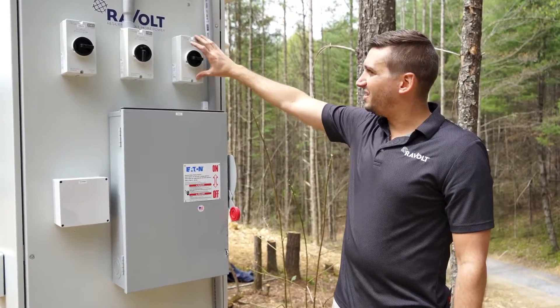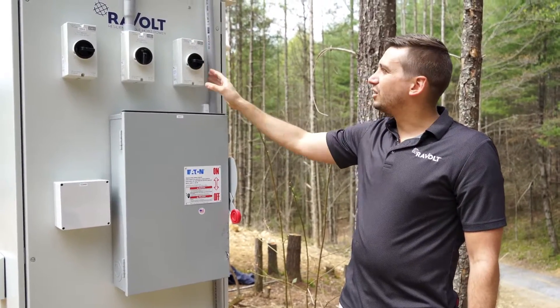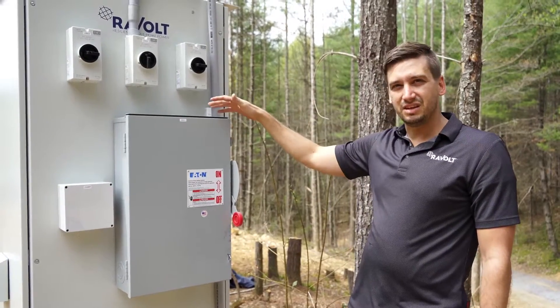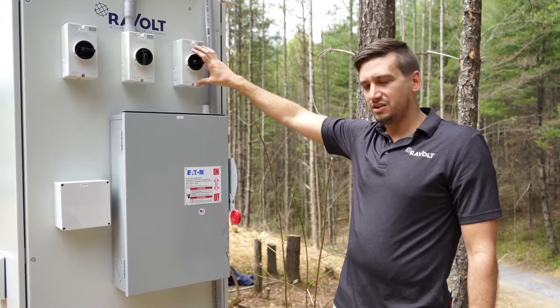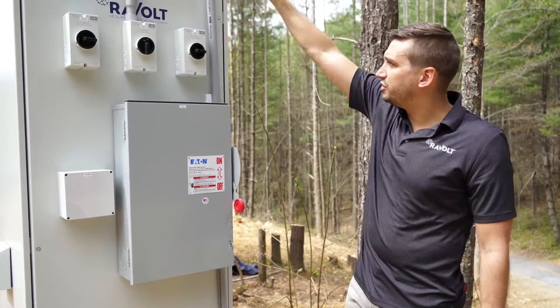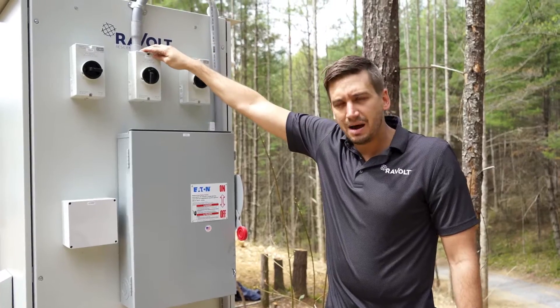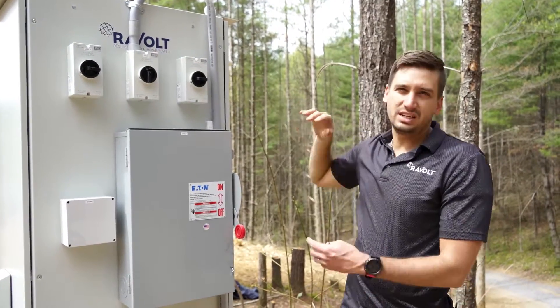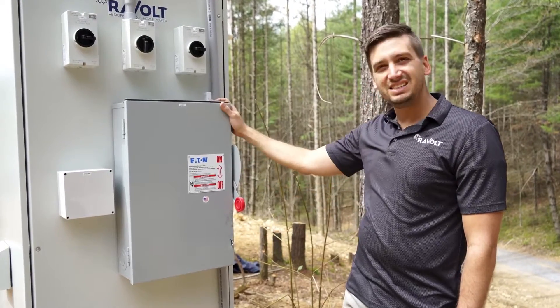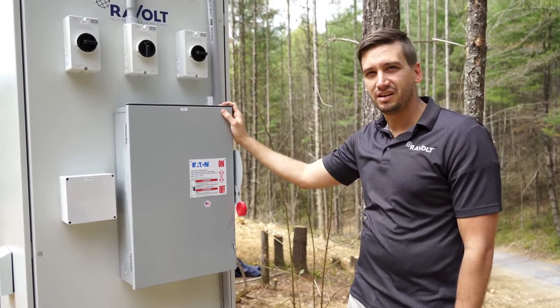Also on this side of the equipment are three PV disconnects that are already pre-wired from the MPPTs of the inverter out to the outside of the equipment. All the customer needs to do is bring a single piece of conduit in and land on the top of the PV disconnects — they don't need to go inside the box for any internal connections. That covers the AC and DC input portions of the Ravolt system.